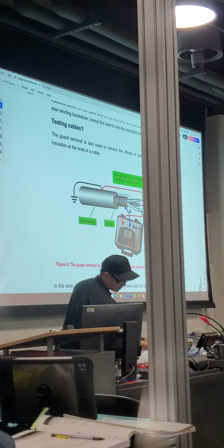So we're looking at this configuration here. I'll separate them out a little better so you can see, but the main setup with the black and red leads hasn't changed. We're still looking at the tape shield, still the cross-sectional representation here. We still have our black lead on the main current carrying conductor. So what formerly tested bad, even though we know it's good from our previous test, we want to prove that out. In this case, it's as simple as a conductive braid around the surface where we think the unintended path is being created, and this one's being guarded out.